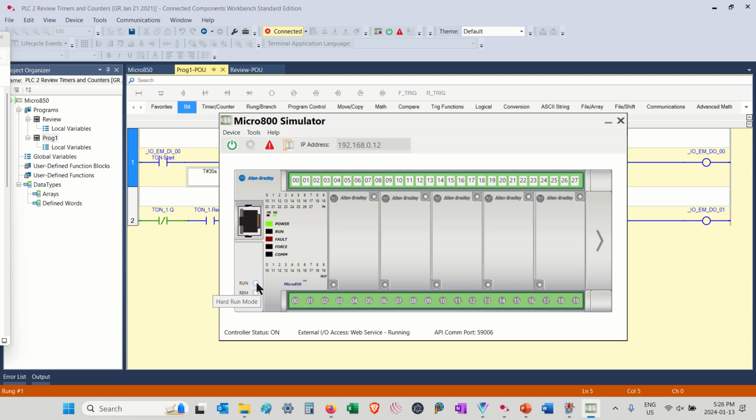Now, normally what you do is you go into run program mode, back and forth a couple of times, and that usually clears it. But just as fast as you clear it, all too often it will come up again. So if it's doing this on a regular basis, it's very frustrating to understand and figure out why it's doing it and how to correct it. So I'm going to show you, it's not that difficult. You only need to get access to the task manager.